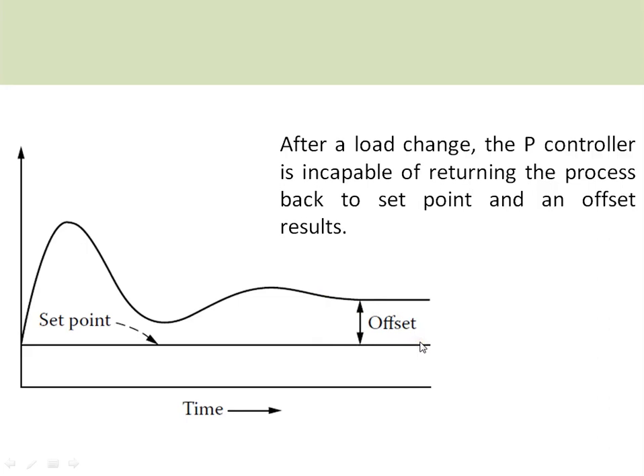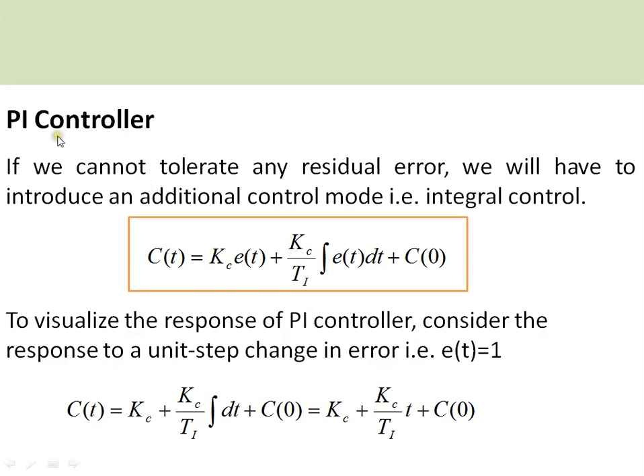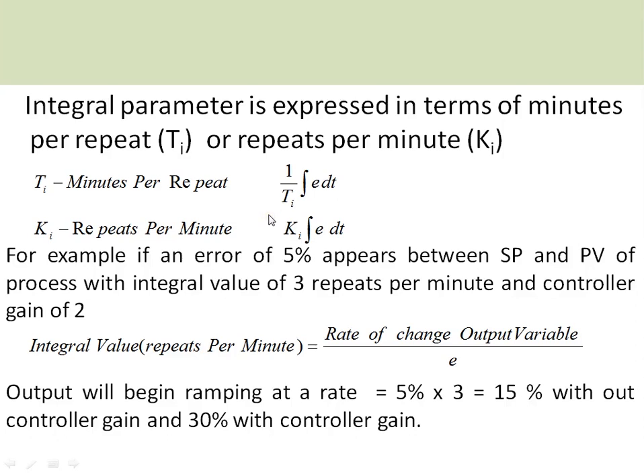The steady-state error can be eliminated by using the integral controller. The proportional plus integral (PI) controller equation is: c(t) = Kc × e(t) + (Kc / Ti) × ∫e(t)dt + c(0), where the first term is the proportional part and the second term is the integral part. The response of the PI controller to a step change in error results in a ramp change in the controller output, since the integral of a step is a ramp. The integral parameter is often expressed in terms of minutes per repeat (Ti) or repeats per minute (Ki).